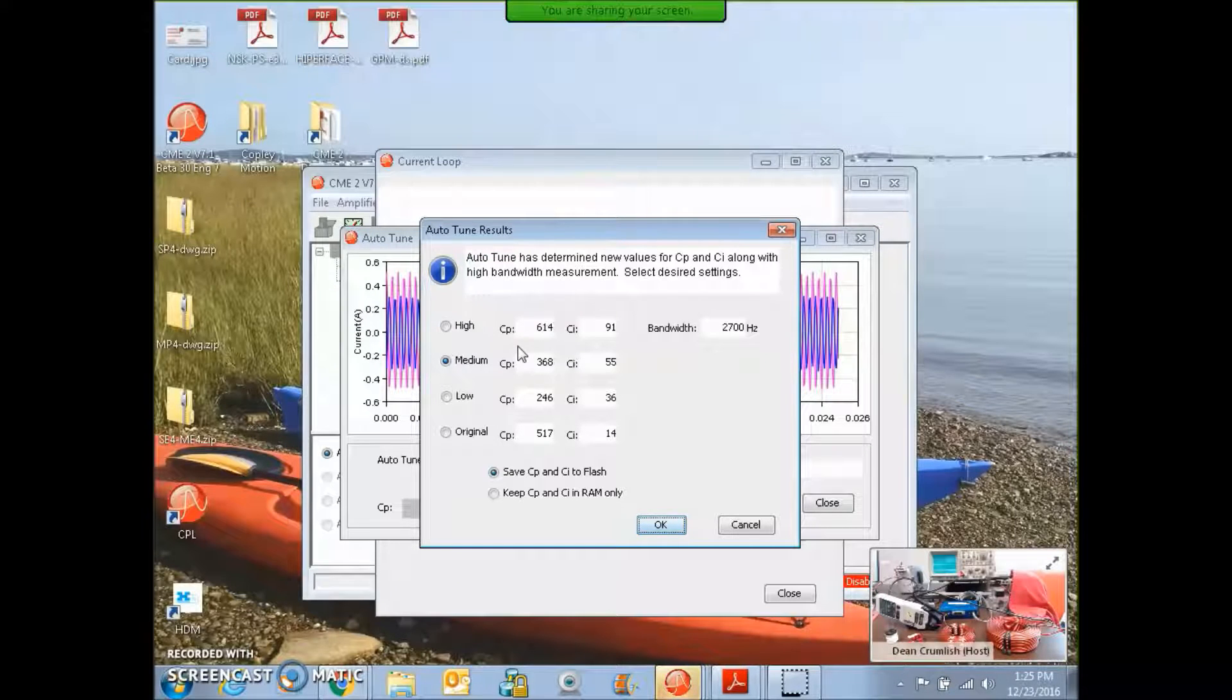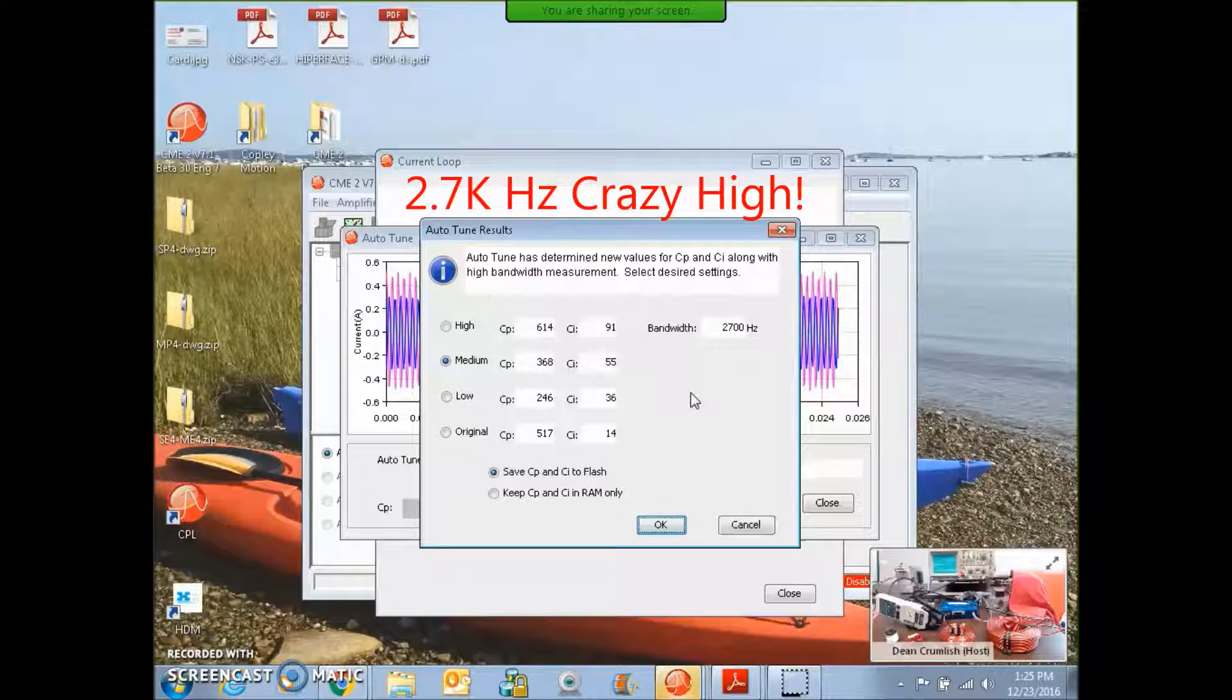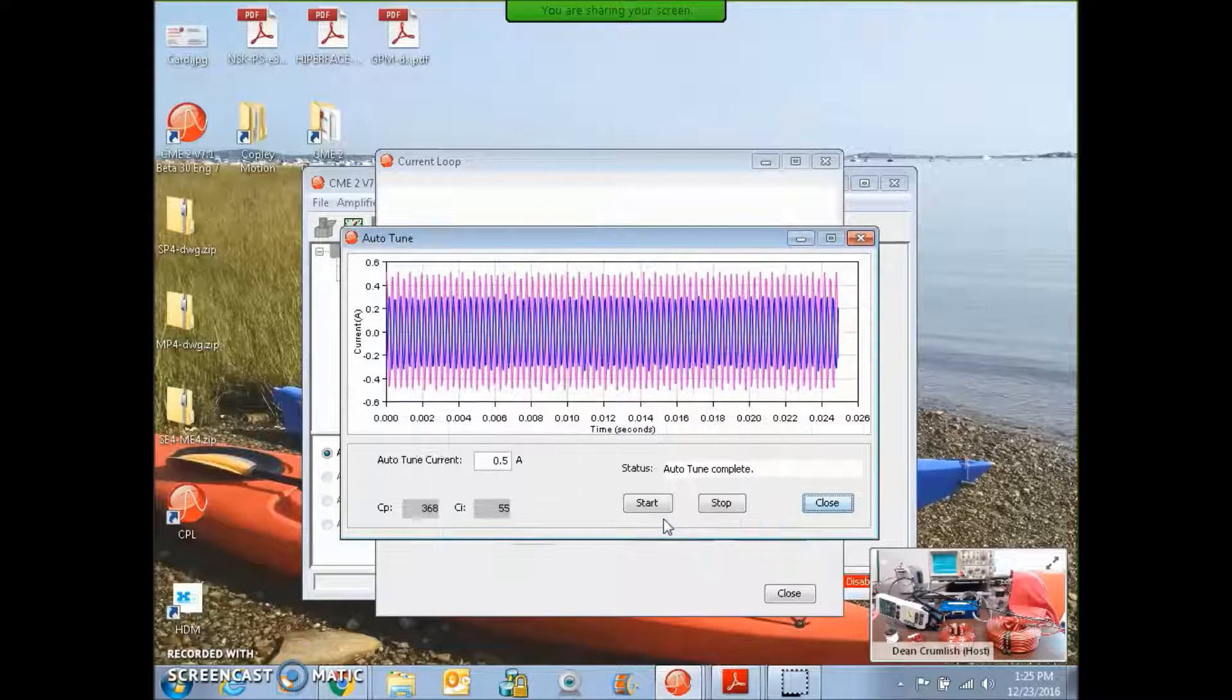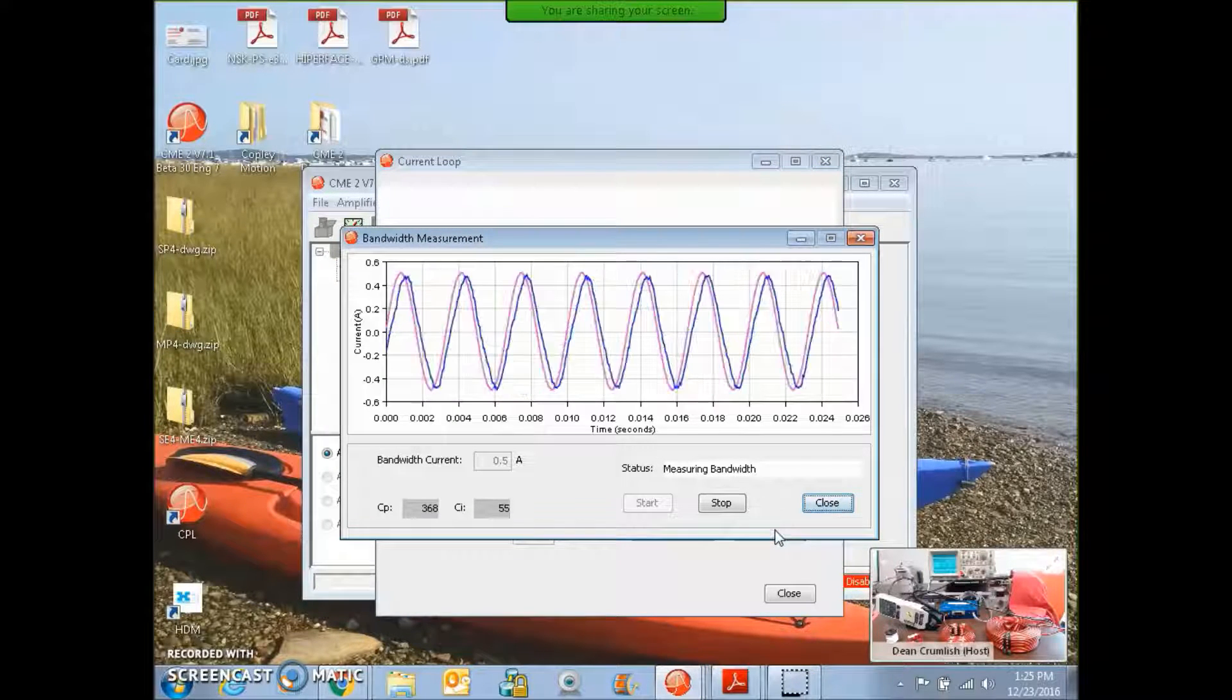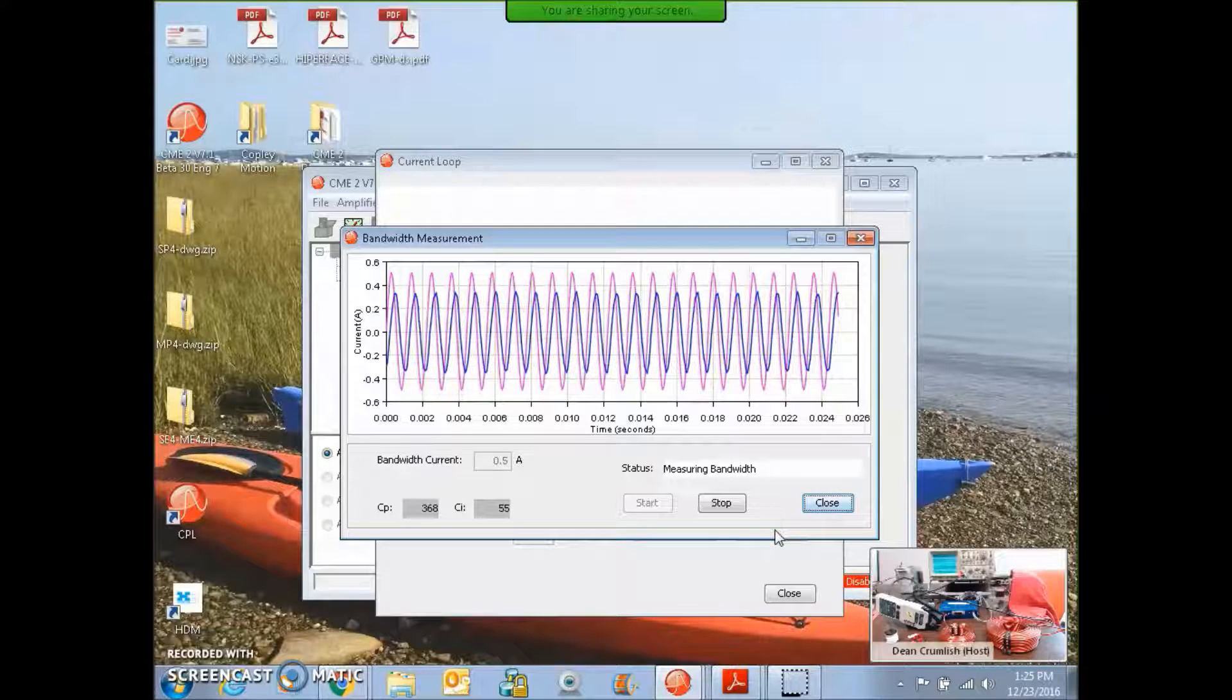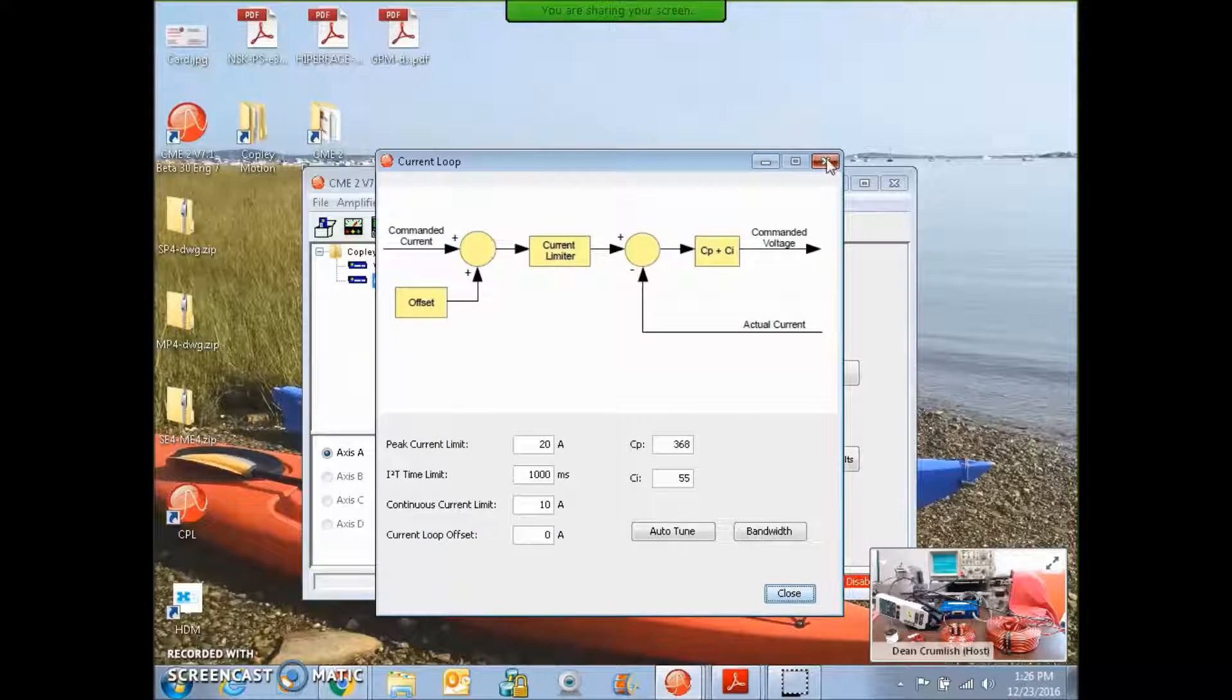The auto tuning is calculating the bandwidth by doing some testing. The high current loop bandwidth is what we tune for in the auto tuner. That's 2.7 kilohertz of current loop bandwidth. That's more than we need for a servo application. But CME2 selects the medium values which give us a current loop bandwidth of a more reasonable value. The calculated values were pretty good. The auto tune values may seem a little better. Maybe it's a little less bandwidth. 800 hertz of current loop bandwidth from the auto tuner.